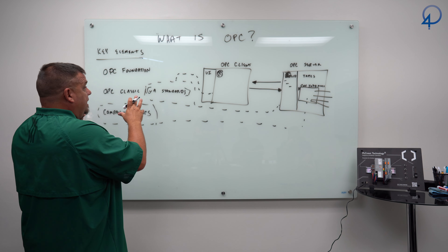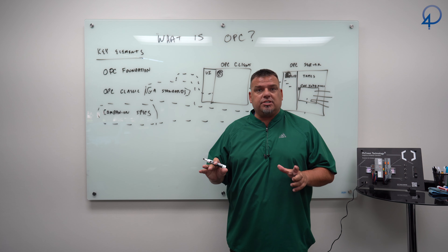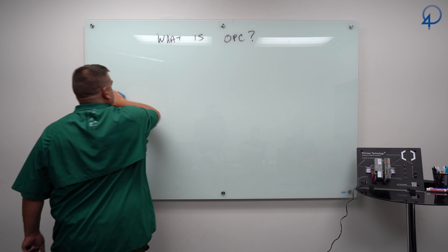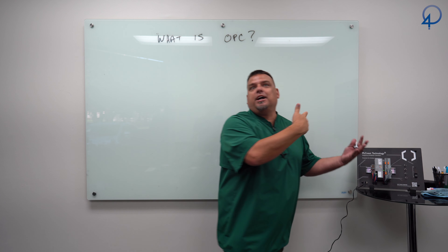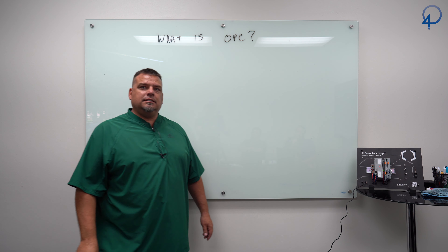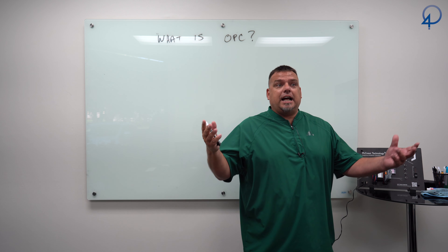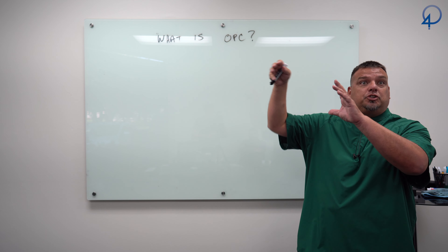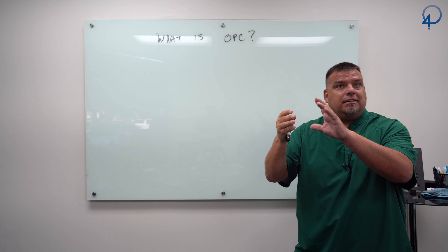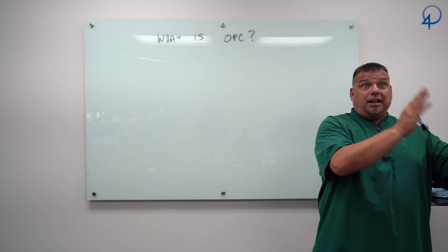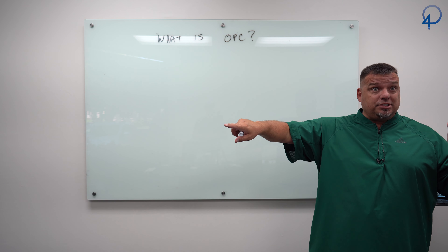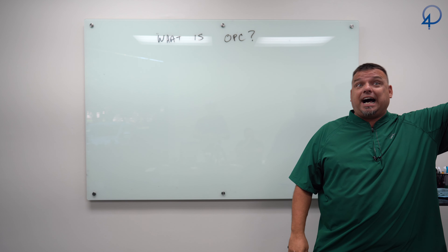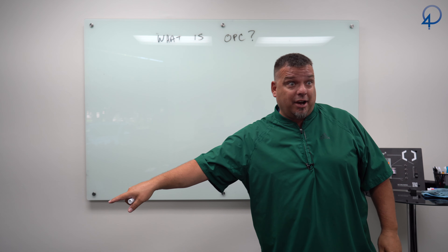That's how OPC works in nearly all use cases — a great example of an OPC use case. What's the problem? You selectively pick components of the specification to build your application. I only used the pieces of the spec I needed for the use case. It's linear integration — data from the machine to my OPC server, then to my OPC client. I have to allow my client permission to connect to my server and open inbound ports, because the connection is instantiated by the client. The response comes from the server, but the connection is instantiated from the client.